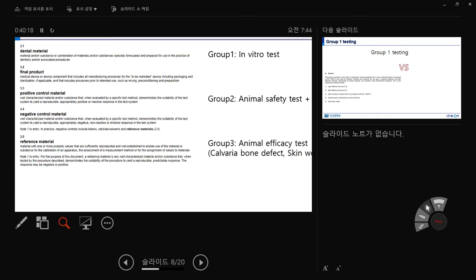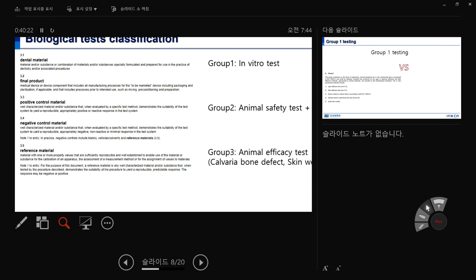Dental material is defined as a material, substance, or combination of materials specially formulated and prepared for use in the practice of dentistry. Medical biomaterial is similar. The 'final product' is the product to be marketed. The 'intermediate product' is, for example, before ethylene oxide sterilization. After sterilization and packing, it becomes the final product. Always evaluate using the final product, not the intermediate product, because something may change during final packaging or sterilization.